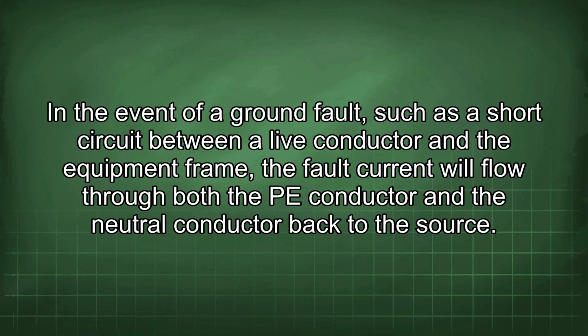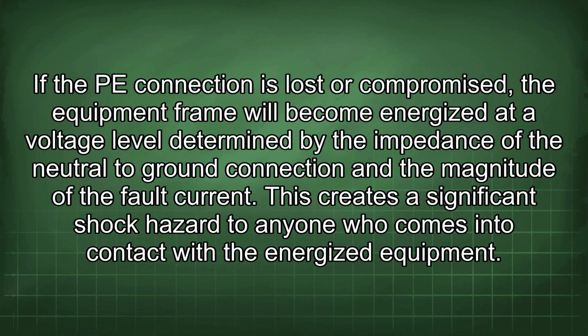In the event of a ground fault, such as a short circuit between a live conductor and the equipment frame, the fault current will flow through both the PE conductor and the neutral conductor back to the source. If the PE connection is lost or compromised, the equipment frame will become energized at a voltage level determined by the impedance of the neutral to ground connection and the magnitude of the fault current. This creates a significant shock hazard to anyone who comes into contact with the energized equipment.